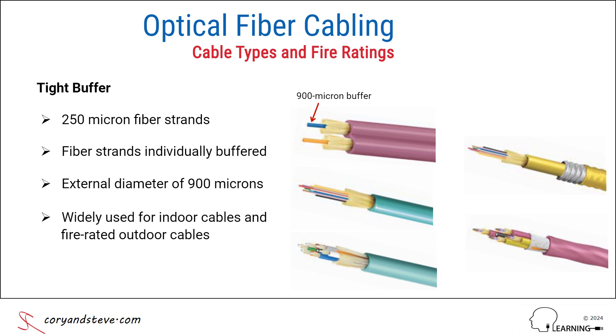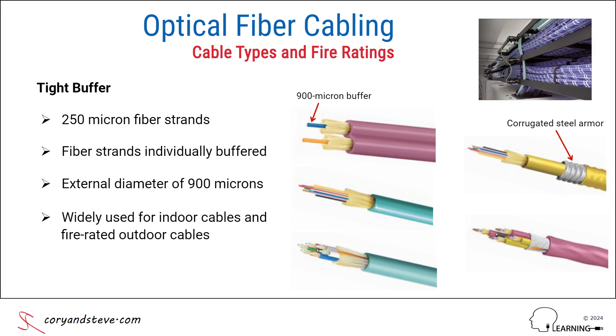As with loose tube cables, additional physical protection for both indoor and outdoor tight buffer cables can be provided by a layer of corrugated steel armor between two layers of jacketing. Armored indoor cables are ideal for use in shared cable trays, where they may end up beneath other heavy cable bundles. In such cases, the armoring prevents excessive signal loss due to the higher crushing forces along the length of the fiber cables.